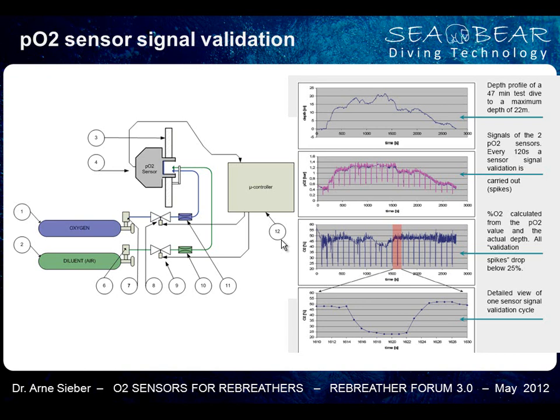During the dive, I think it was 120 seconds, we injected either oxygen or diluent onto the sensor membrane, depending on which depth you are. You can see this in these small spikes. Each of these small spikes going down is an injection of diluent. In that case it was air, onto the sensor membrane.